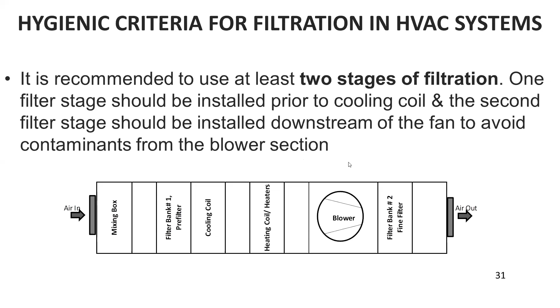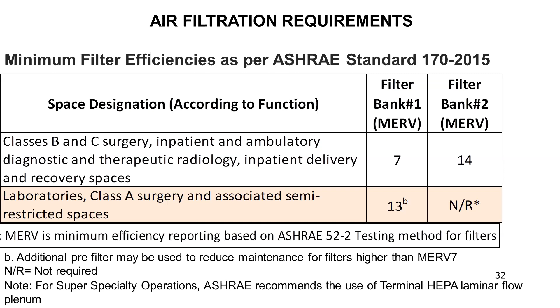As I clarified, you've got all sorts of operations. It's not that everything is a specialty operation. So if it is class B and C surgery, you need MERV 7 and MERV 14 filters. That's good enough. You don't need to put HEPA filters. Laboratories, class A surgery, you need MERV 13 filters. Then it's only in super specialty rooms that ASHRAE recommends the use of terminal HEPA laminar flow plenums. So just be aware of that. For every operation you don't need laminar flow and so on.